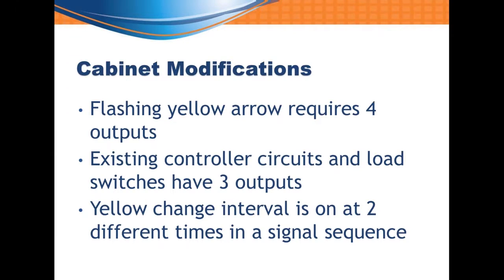Now we have to talk about the cabinets. Something that makes flashing yellow arrow unique is that each phase requires four outputs. In the past, controllers and circuits in the cabinet were designed for three outputs — red, yellow, green, or walk and don't walk for pedestrians. Now we had to create a virtual four-position load switch and controller circuit in the cabinet, which meant two different load switches doing the function of flashing yellow arrow. Also, the yellow change arrow is on at two different intervals in the sequence — after the green arrow and after the flashing yellow — so they have different requirements for what they can be on with simultaneously. This required a controller and MMU intelligent enough to handle this and keep it out of flash when the arrow came on at different times.